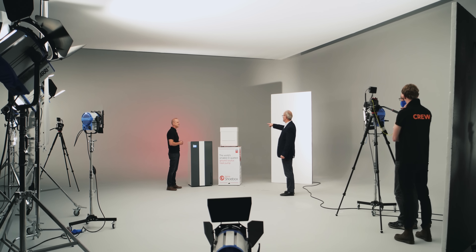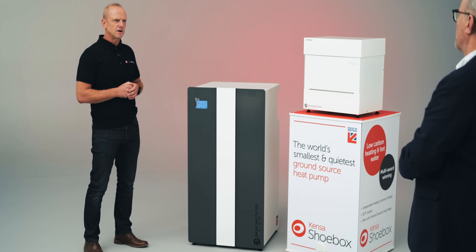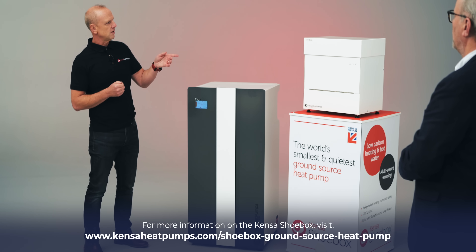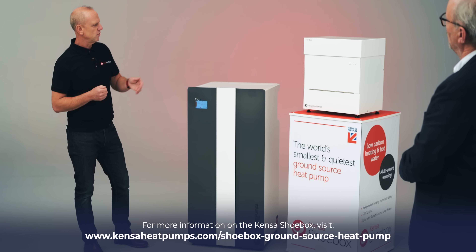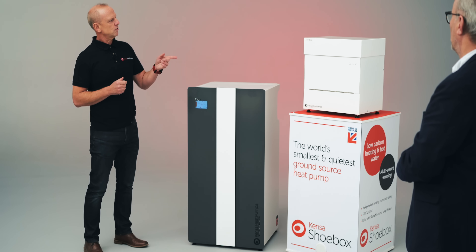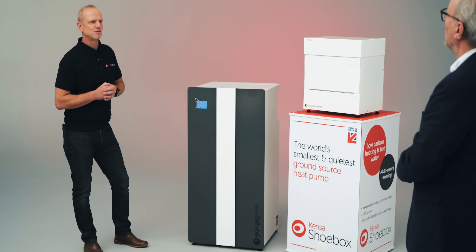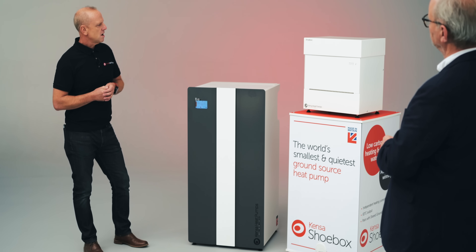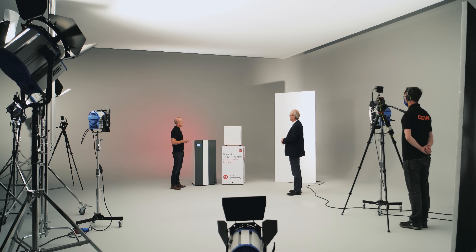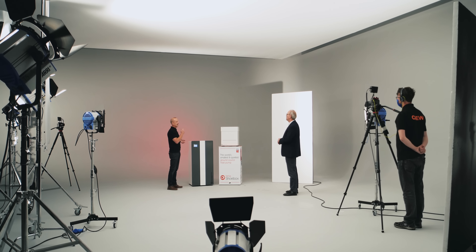This is considerably bigger than the shoebox. I saw a house recently featured on Fully Charged with the shoebox fitted in — that was one individual home, probably a three-bedroom house. Is that sufficient for that size of property? The EVO range goes up to 17 kilowatt in single phase, and we do make a 15 kilowatt three-phase model, but the shoebox is predominantly used in smaller properties. We make the three kilowatt and a six kilowatt, which is a slightly bigger unit. The project you saw was using a six kilowatt — you can put that in a small property like a bungalow or a flat, including high-rise flats, or you might put multiples in — one in each flat in a block of flats.